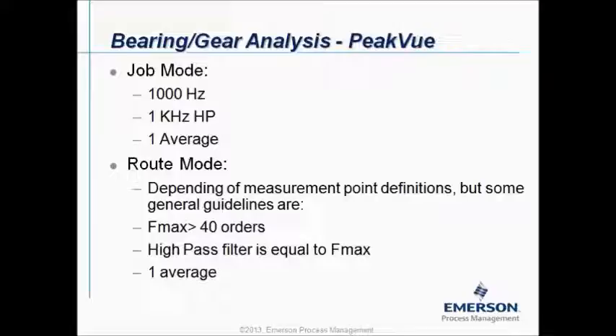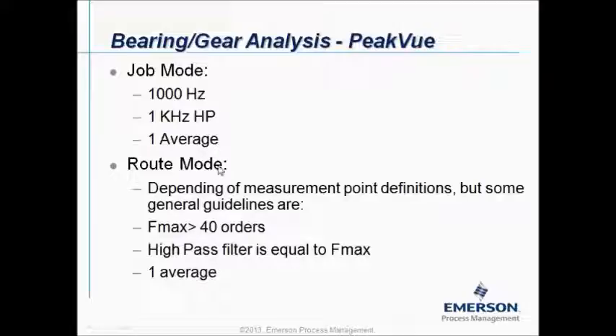PeakVue measurements can be measured in the job mode or in the route mode. If you measure PeakVue data in the job mode and you're using the default setting, it will collect a spectrum up to 1000 Hz with a high pass filter of 1000 Hz and one average. If you collect PeakVue data starting from the route mode, it will depend on the measurement point definitions, but here are a couple of general guidelines. It's recommended to use an Fmax with at least 40 orders as an Fmax or higher.